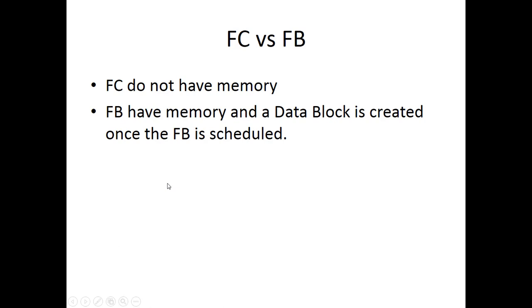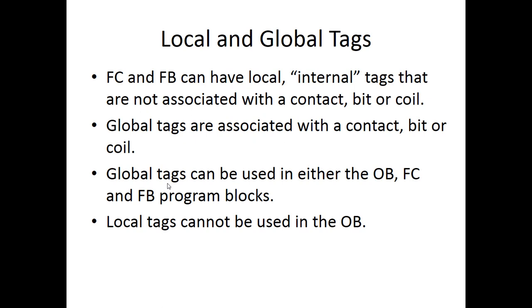Functions do not have memory. FBs have memory, and a data block is created. So once you create your function block and you have all your inputs and it's working, remember you just can't copy the function block — you need to schedule it. You need to add the block because a data block will be created with it. FC and FB can have local internal tags; they're not really associated with a contact, bit, or coil, and you can reuse them a lot.